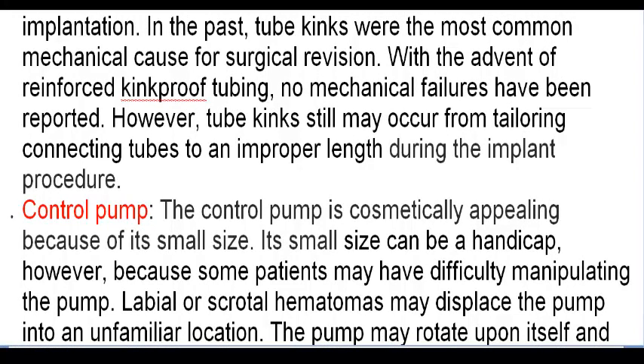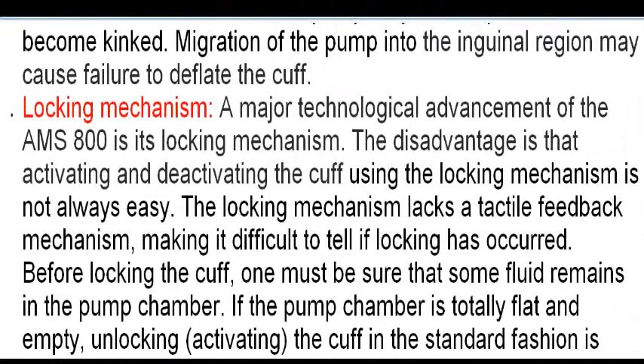However, tube kinks still may occur from tailoring connecting tubes to an improper length during the implant procedure. Control pump. The control pump is cosmetically appealing because of its small size. Its small size can be a handicap, however, because some patients may have difficulty manipulating the pump. Labial or scrotal hematomas may displace the pump into an unfamiliar location. The pump may rotate upon itself and become kinked. Migration of the pump into the inguinal region may cause failure to deflate the cuff.